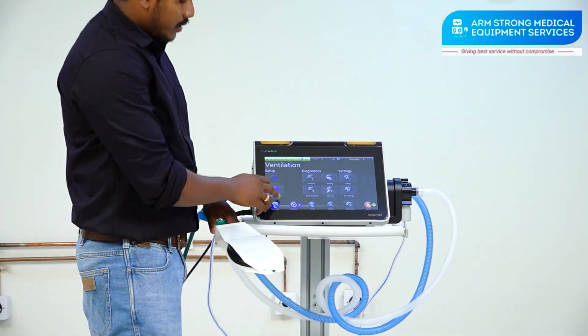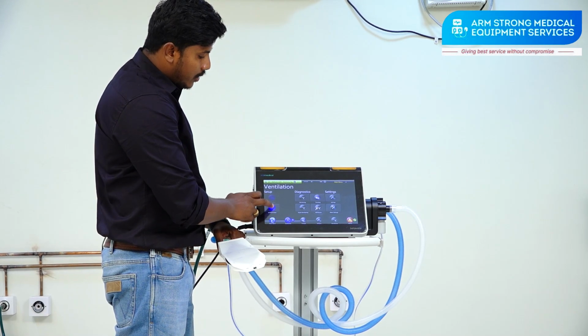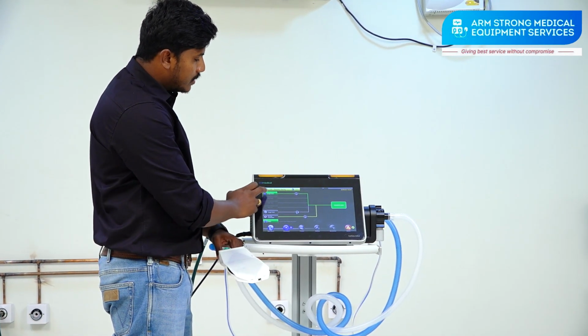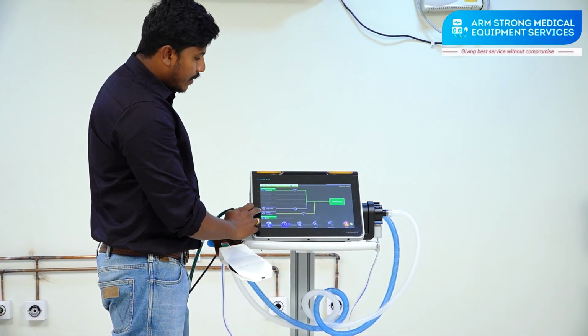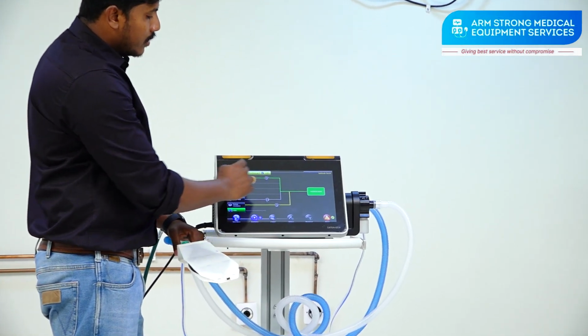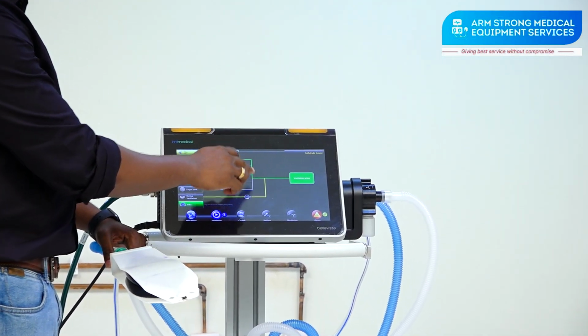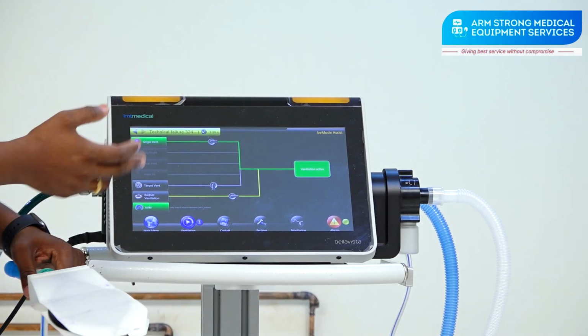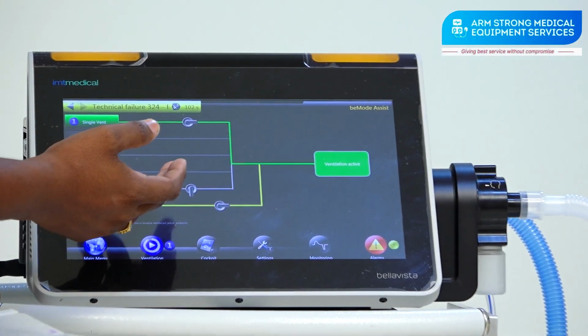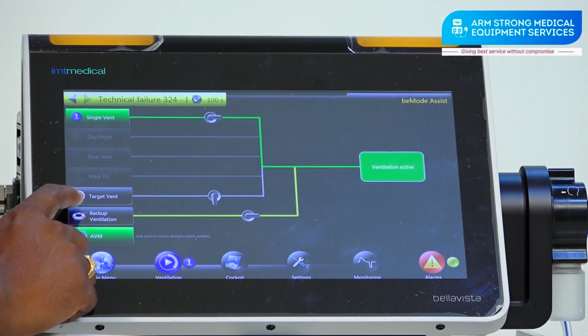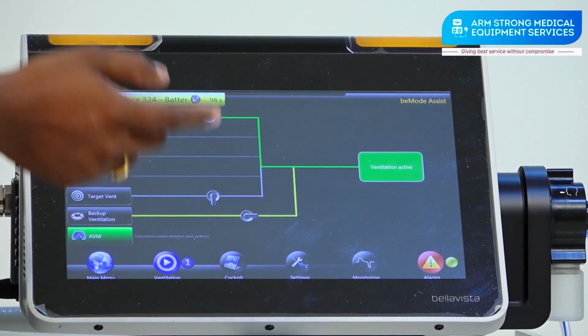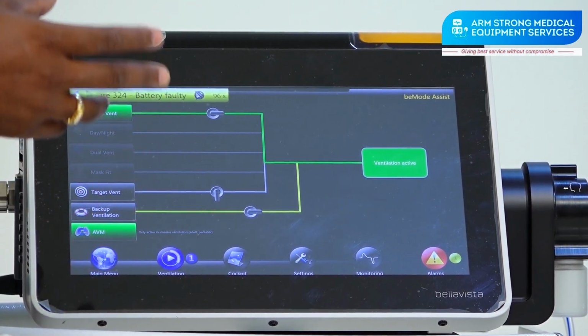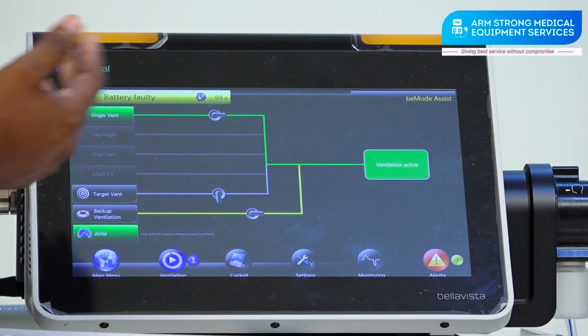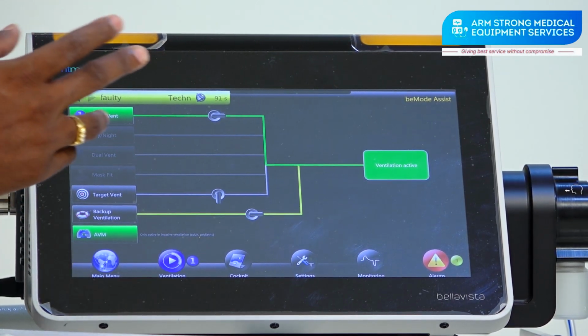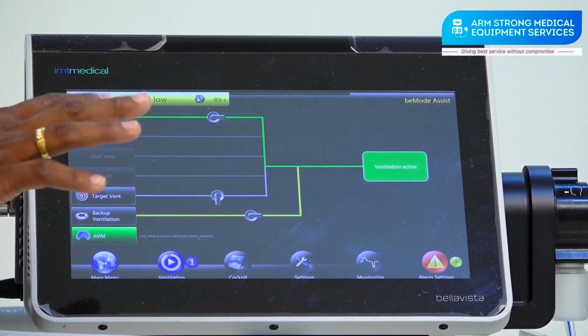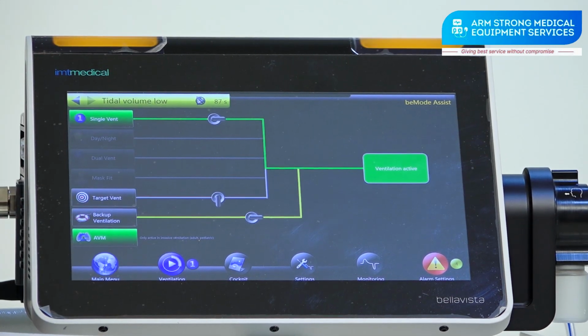See, on this ventilator we have a beMode assist also. See here, beMode means single vent and backup ventilation switched on. In single vent we have a lot of modes like SIMV, VCV, all these modes. And we have CPAP also. In CPAP, backup ventilation is also switched on, and we can select the particular backup mode along with the settings. So if the patient trigger is not there or patient support is not there, it will go automatically to the backup ventilation.